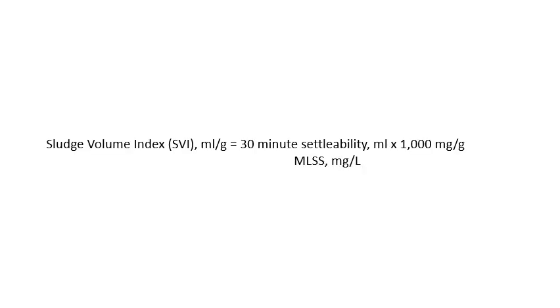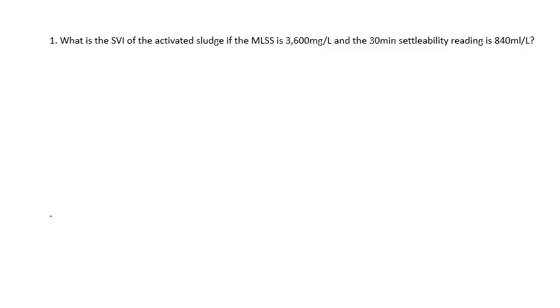The formula for the Sludge Volume Index is off the State of Florida formula sheet they give you whenever you take a test. As always, I suggest if your state gives you a formula sheet, get familiar with it so that you know where to find things and you're not scrambling during a test. The Sludge Volume Index is equal to the 30-minute settleability divided by the Mixed Liquor Suspended Solids times one thousand.